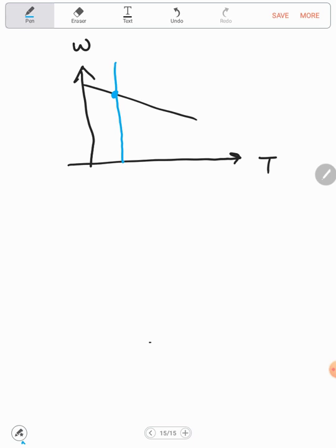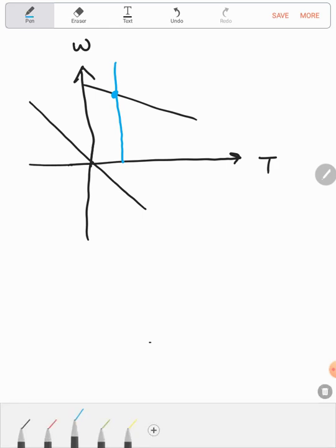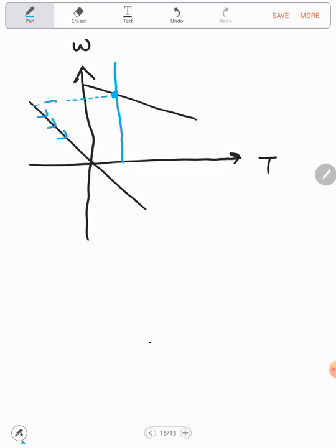Now the first thing, the voltage is 0, which means that all the lines must cross the 0. So crossing the 0, the machine will go following this line until reaching the 0. Now here, if I'm disconnecting the load and engaging mechanical drum, the machine will stop. And this is the idea behind the dynamic braking.